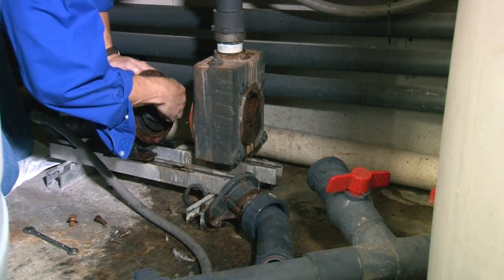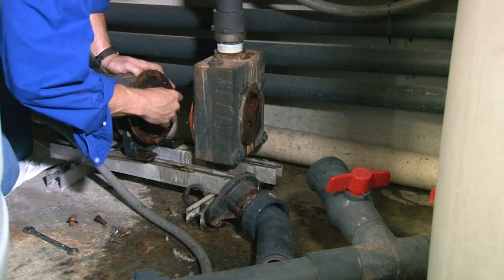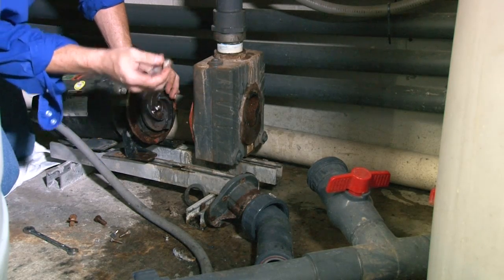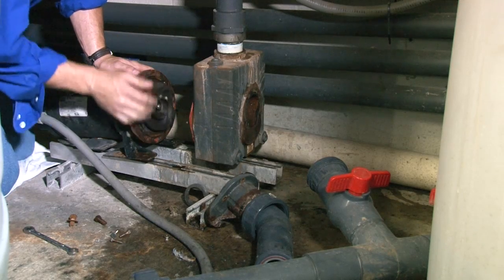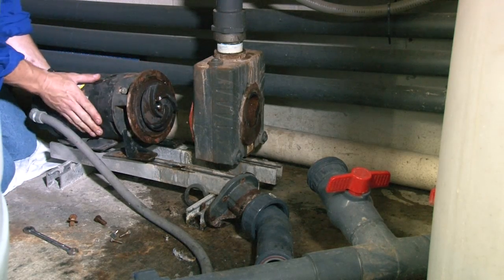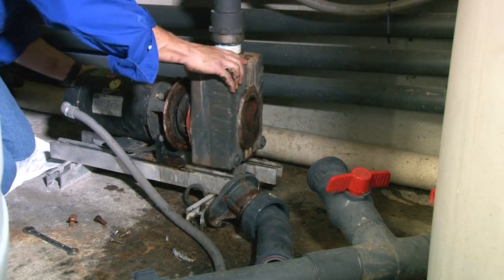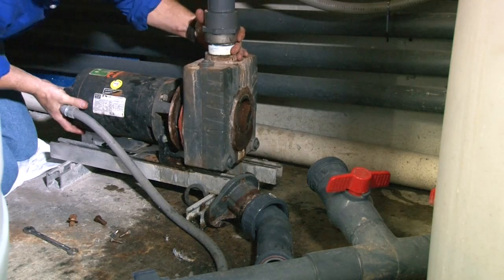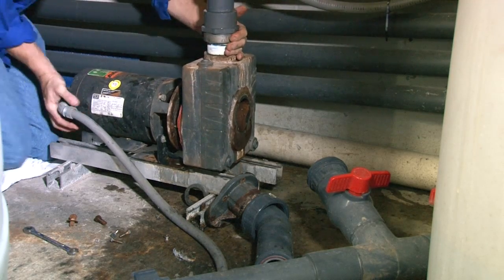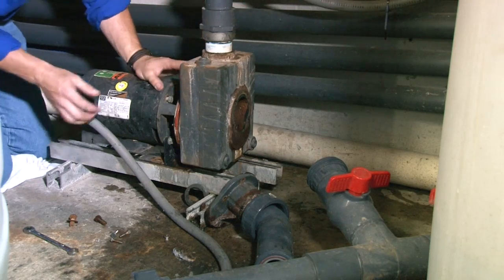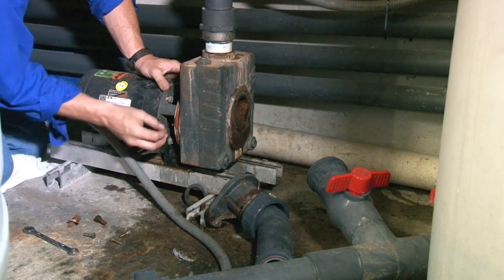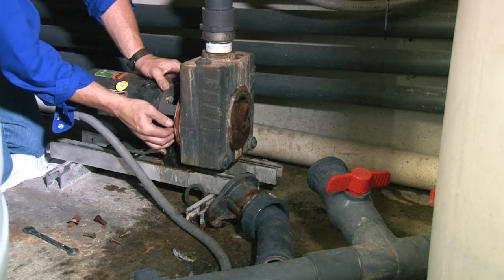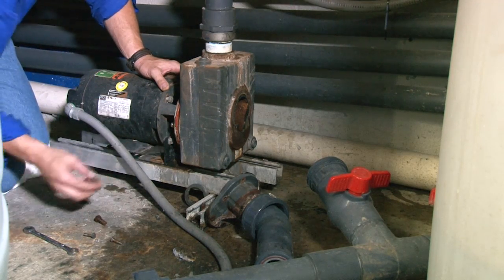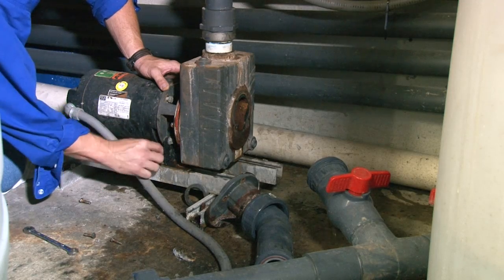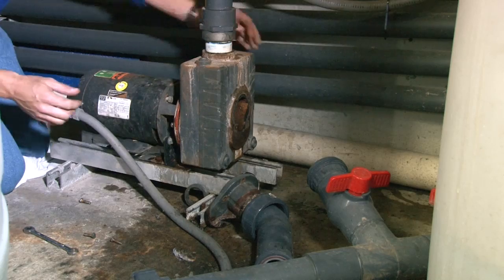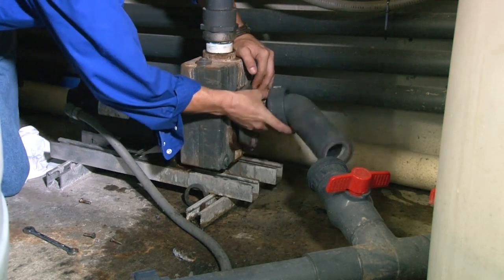I happen to have just a wad of plastic in here. Looks like a plastic cup. So now my clog is clear. I can put my pump back together, and it's just a reverse order. So now I've got the motor shoved back into the pump head. I'll put my 6 bolts back on. I'll put my 4 motor bolts back on, and then I can reconnect my inlet.